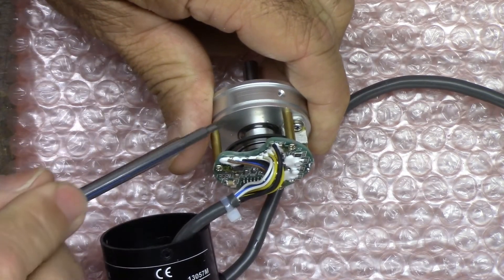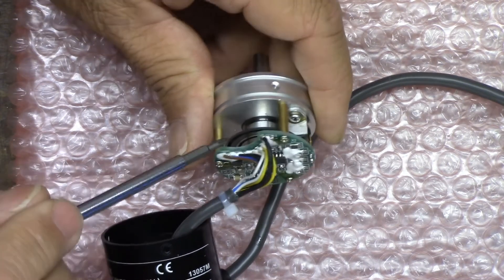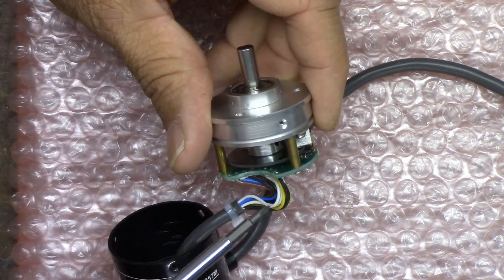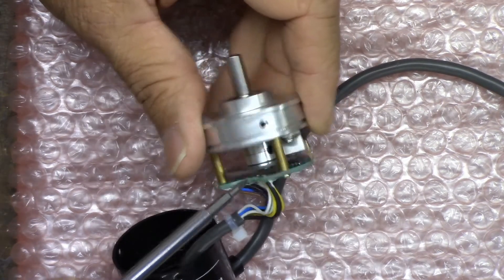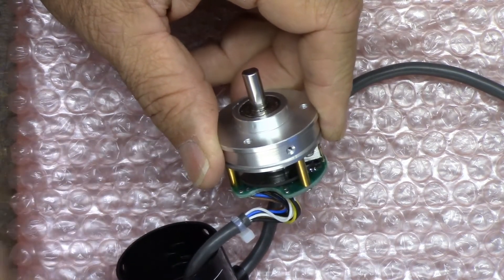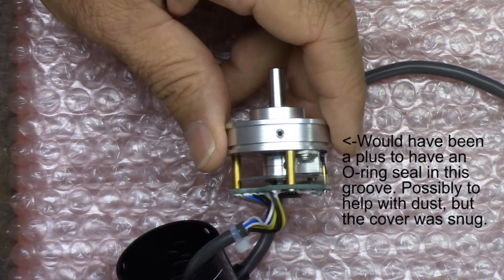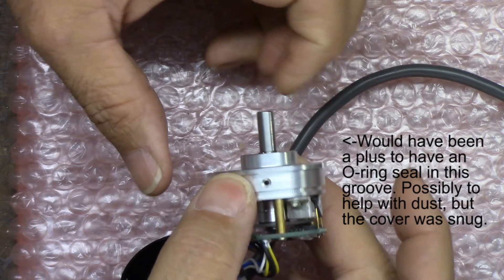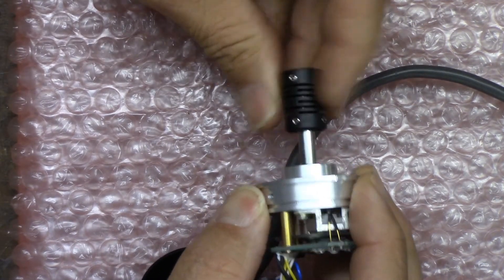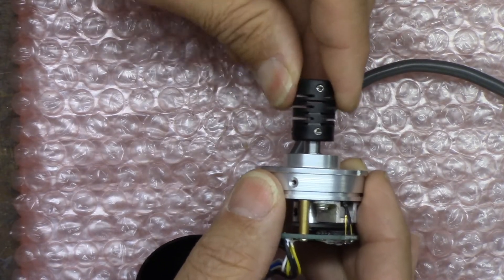If we look in here, there is a bearing on this side - obviously there would have to be. It's quite a bit smaller than the bearing on the outboard side, and that's why you want to run these on a jack shaft using a coupler.